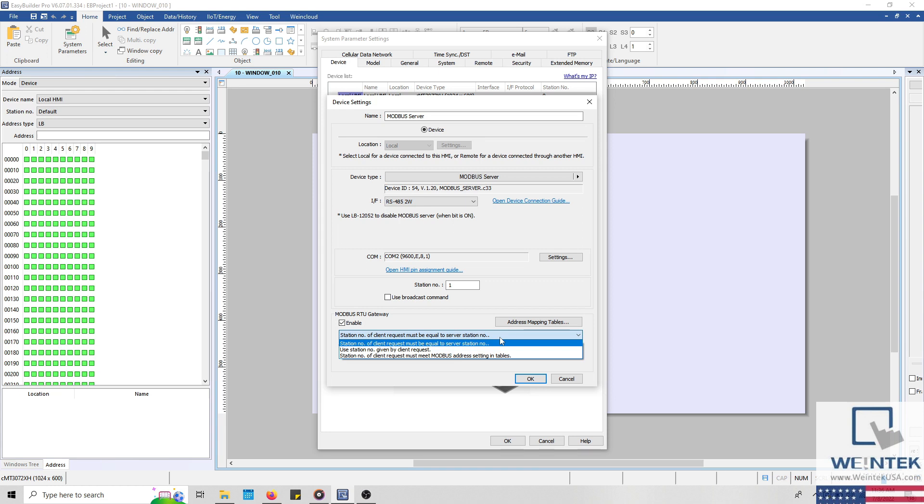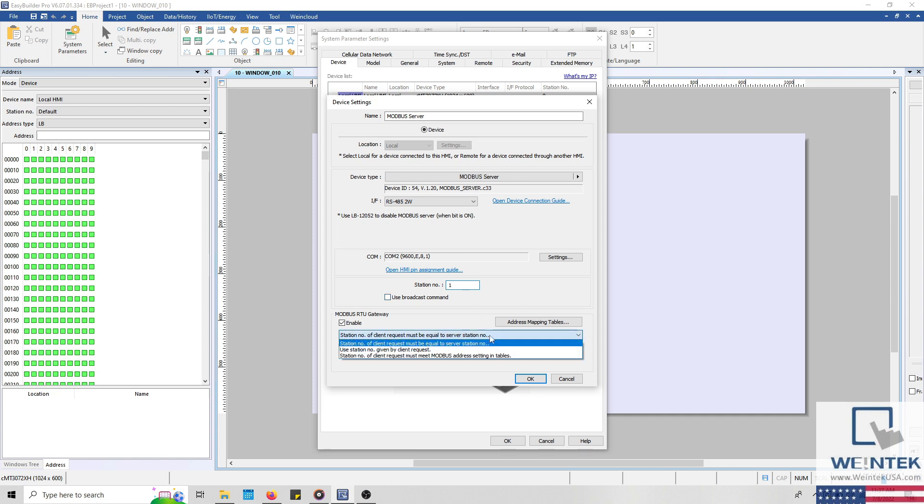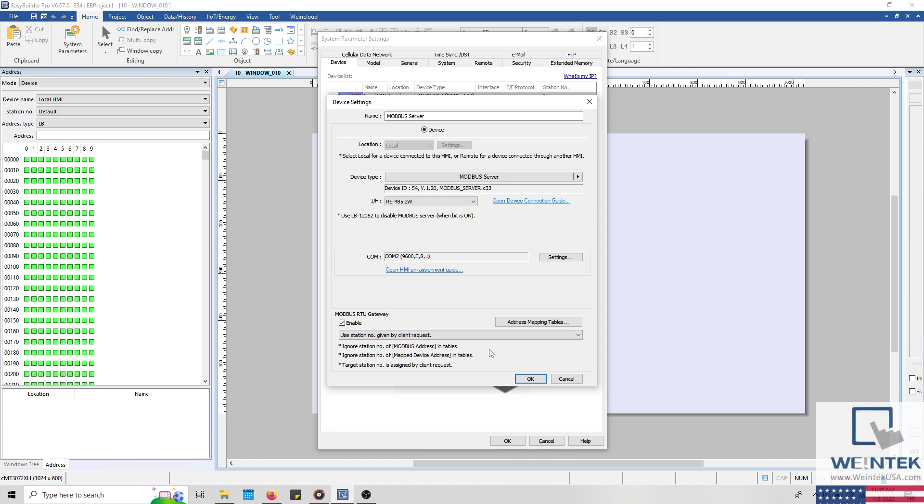For example, while the station number of client requests must be equal to the server station number is selected, the station number within the client request must be equal to the station number configured within the station number entry box above. Whereas use station number given by client request will allow the HMI to use the station number of the Modbus client request.